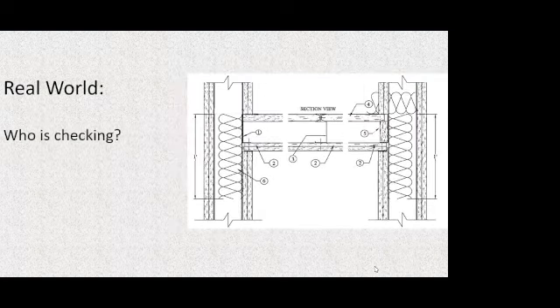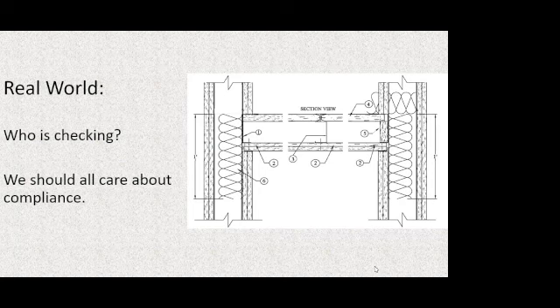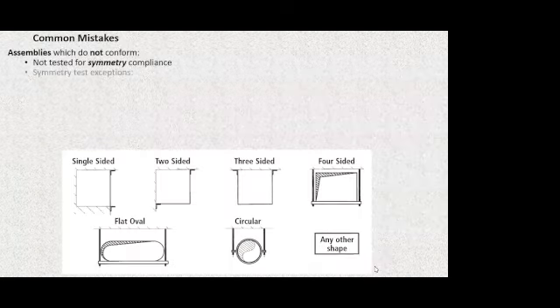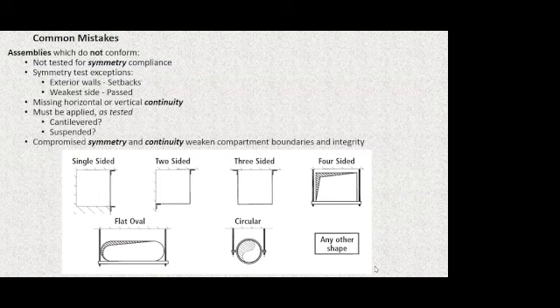That should look like this, where the entire assembly is properly symmetry tested and performing for all fire exposures on either side. That's what's in the code. That's what needs to be done. And our fire rated duct systems need to be equivalent to that. And that means, quick recap, we need to vet out and eliminate the ones that are not tested for symmetry compliance. Duct A has no legitimate use in the code.